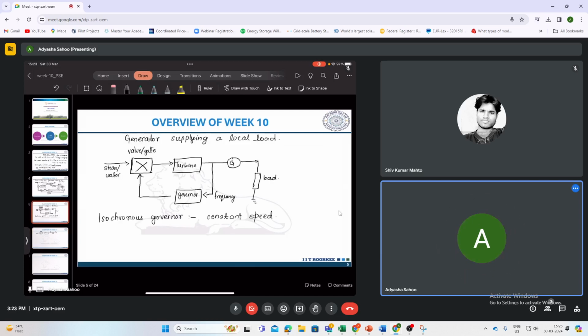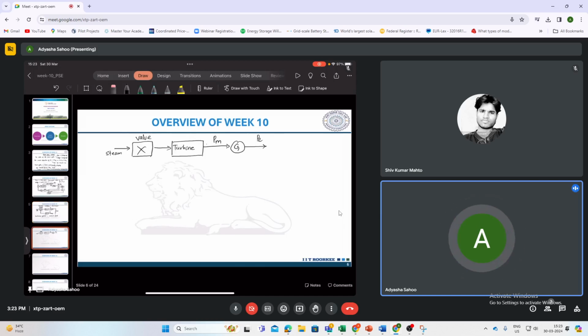So if we see the block diagram of that isochronous governor, it is basically that the steam, this is your valve, turbine, generator, then your load. So here you're giving the mechanical input to the generator and getting the electrical output like it was here. So if this is the mechanical torque, then this is your electrical torque. Similarly, here also.